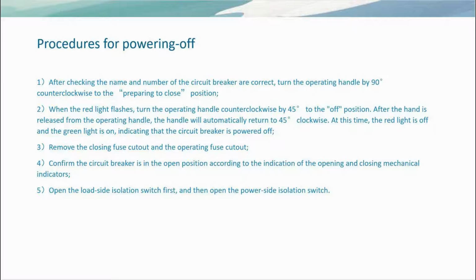powered off. 3. Remove the closing fuse cutout and the operating fuse cutout. 4. Confirm the circuit breaker is in the open position, according to the indication of the opening and closing mechanical indicators. 5. Open the load side isolation switch first, and then open the power side isolation switch.